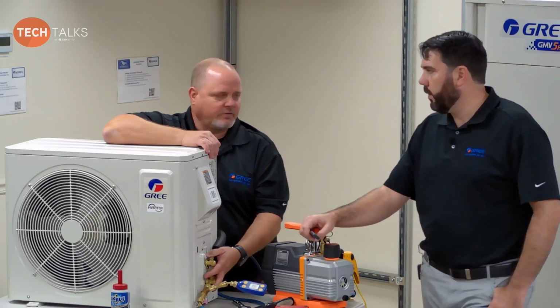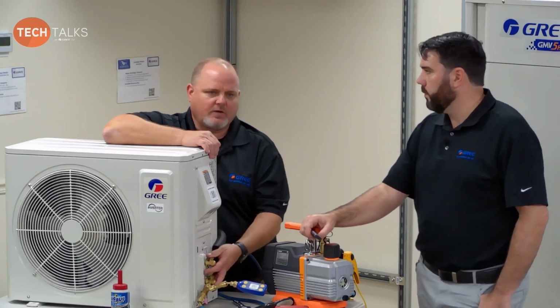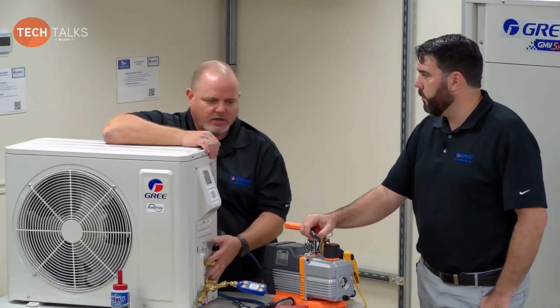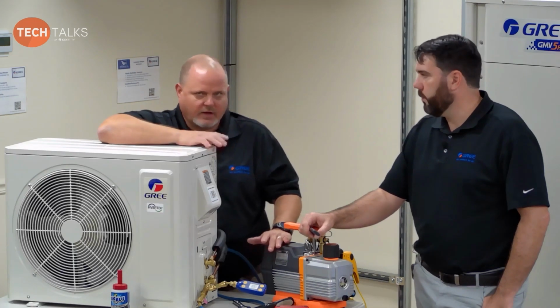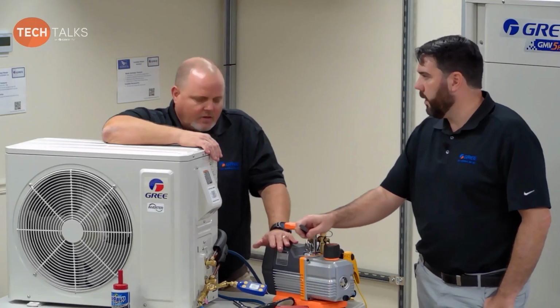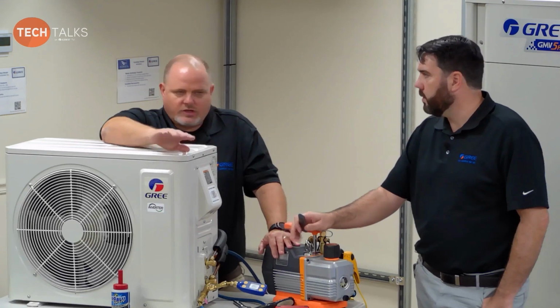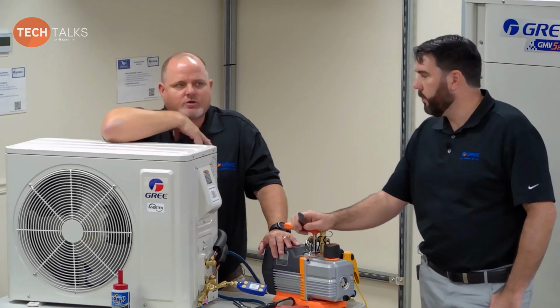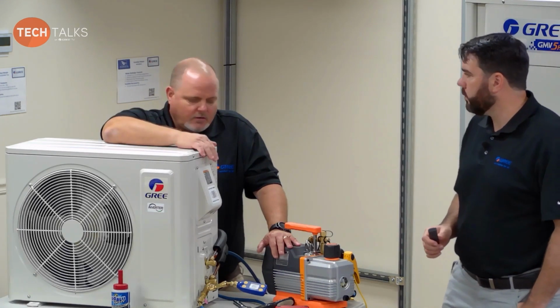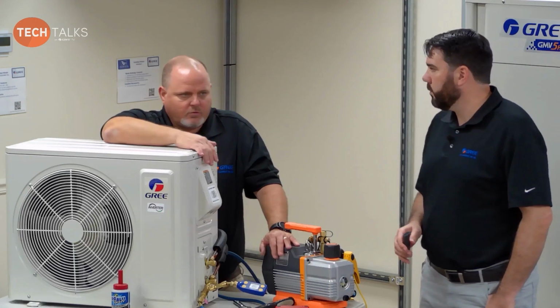I'm dealing with my A circuit. Find the leak on A, get that corrected. Now I'd go back and pull a vacuum on that one. That way, individually, you've isolated it to one circuit at a time as to whether or not you've got leaks, in case there is a leak. That makes perfect sense. To each their own. I personally would do each one separately, but you can pull from multiple ports if you want.